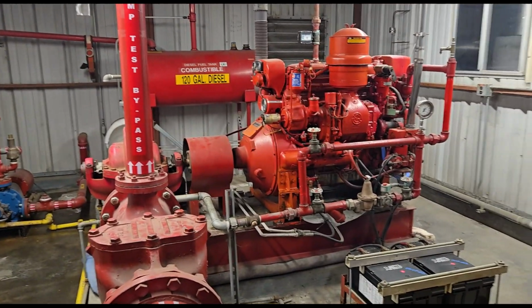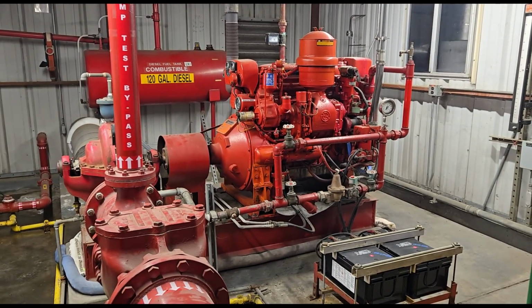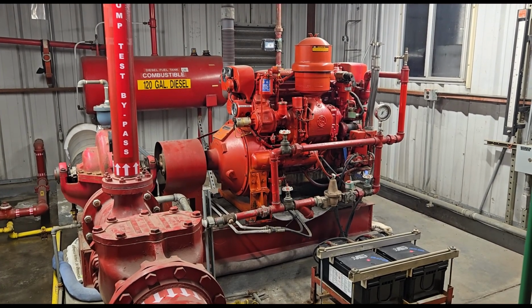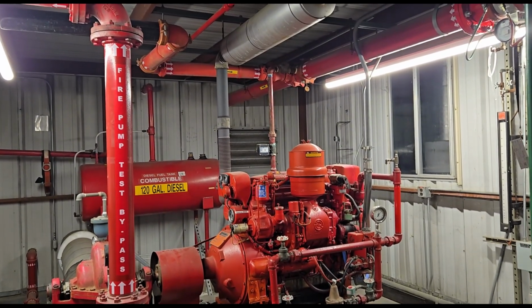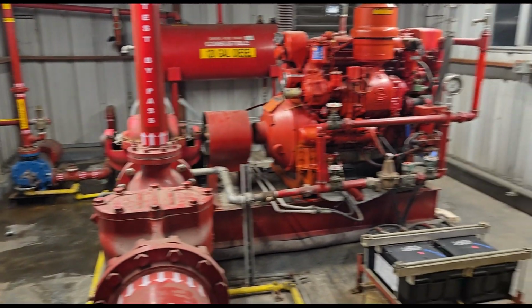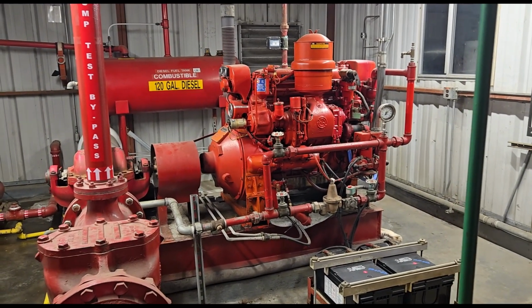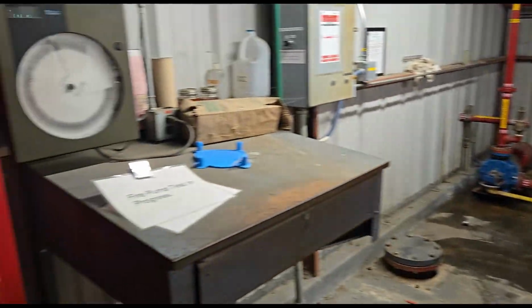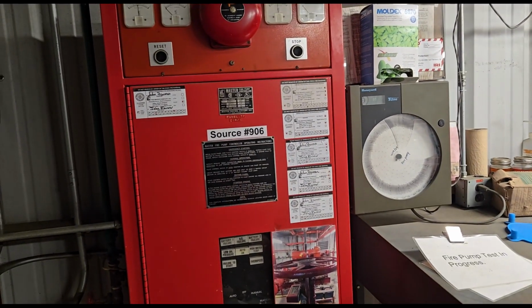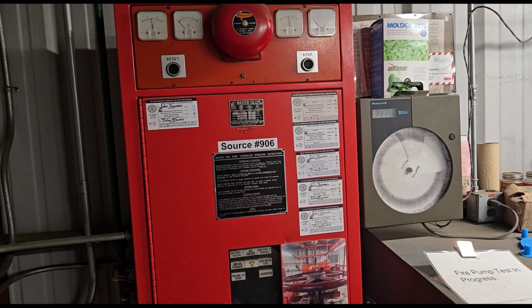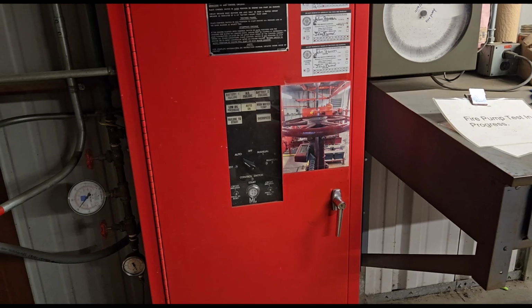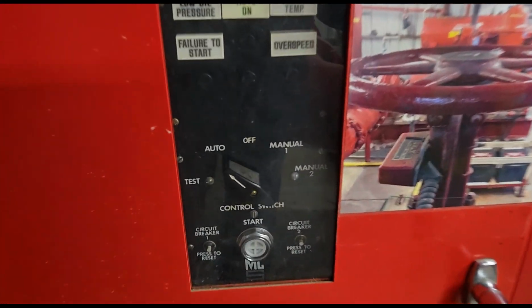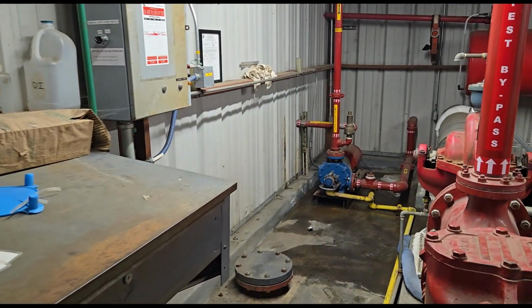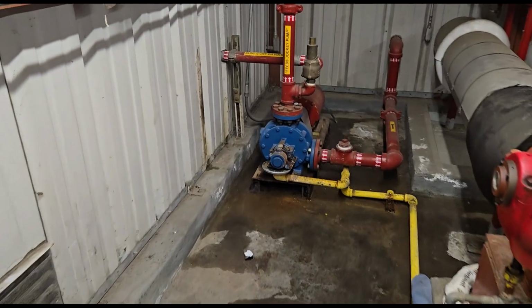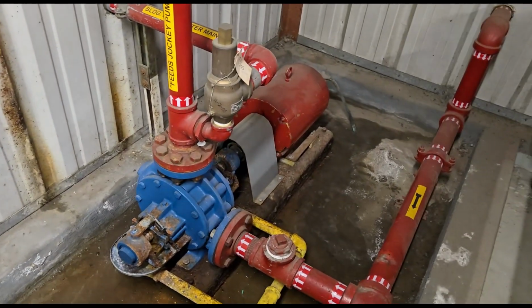If the fire pump is running, it could overheat, it could cause an issue. Like I said, the pipes could get over pressurized, the PSI could get too high and pop a sprinkler head. So that's all under the contract of the sprinkler technicians to do the testing on the pump. For me, I'm just testing the electronics of the sprinkler system. So I want the flow switches and tamper switches to activate and report to the fire panel. Since I don't need the fire pump to be on, I'm going to be turning it off with the auto off feature here. And I'm going to run everything off this little jockey pump here. So this is going to be doing all of our work for our flow testing.